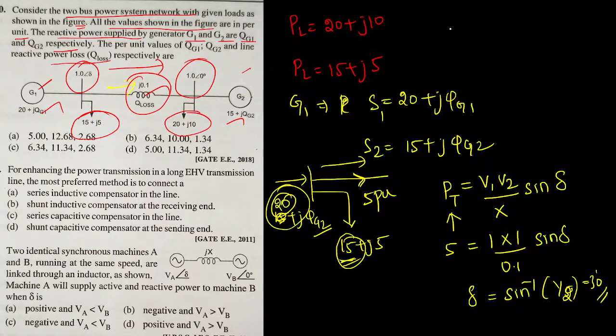Once you have calculated the value of delta, from this you can calculate how much reactive power is sent through the transmission line from the sending end. What is the formula to calculate the sending end reactive power? Vs square divided by reactance X, minus the sending end voltage times the receiving end voltage divided by reactance X, into cos delta. Correct, sir? The reactance value is 0.1 and the voltages are 1, so 1 by 0.1 will be 10, minus 1 into 1 divided by 0.1, that is 10 into cos 30, which is 0.866, that is root 3 by 2. So 10 minus 8.66 gives 1.339. That is the reactive power being transmitted from the sending end, approximately 1.34.